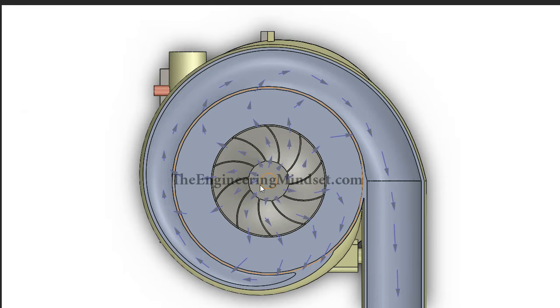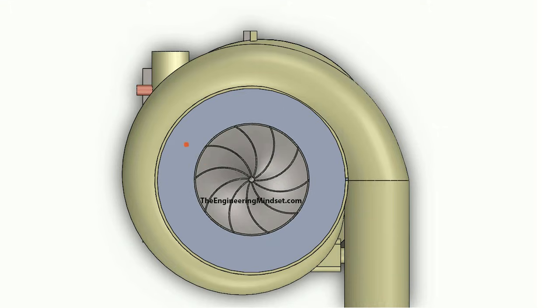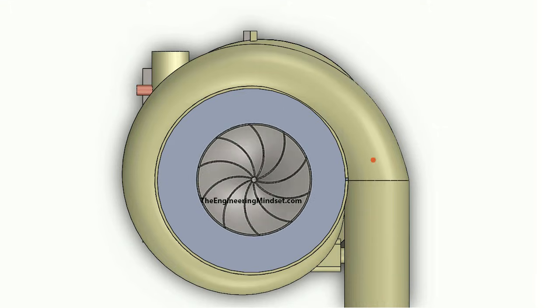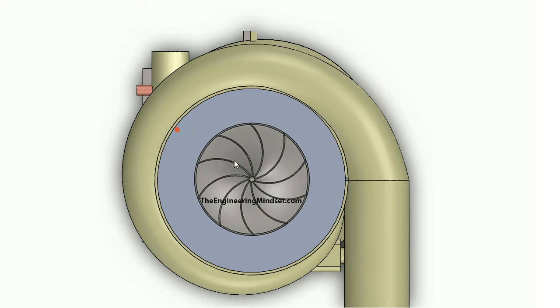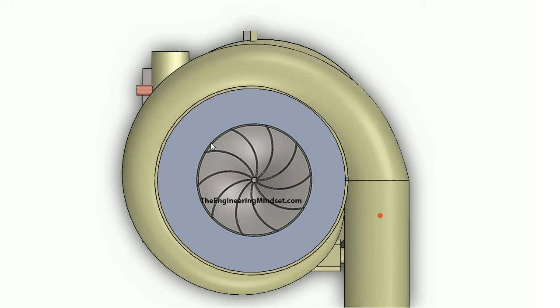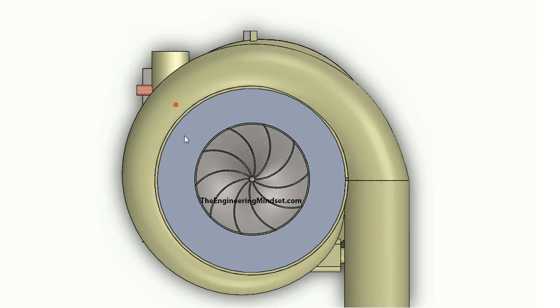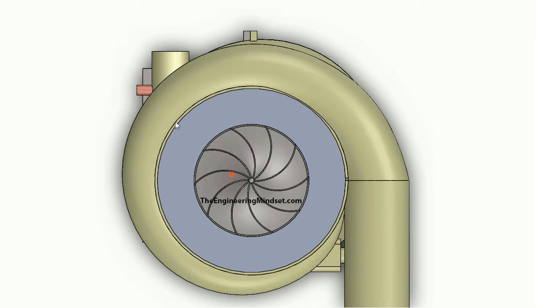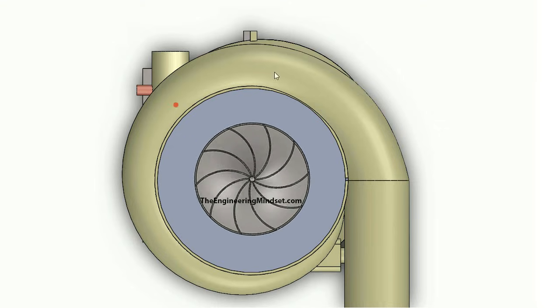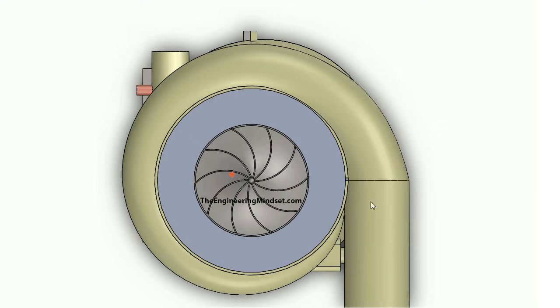And there's another view of it there with the arrows indicating the flow path as the particles of the refrigerant are split up and forced through these different sections as this is rotating also at a very high angular velocity. And just the diagram here to show you an animation, even to show you kind of the flow path of that, so you can see it's being flung off of these blades here and pushed out, and then that momentum is forcing that all the way around the volute and building up that head pressure.